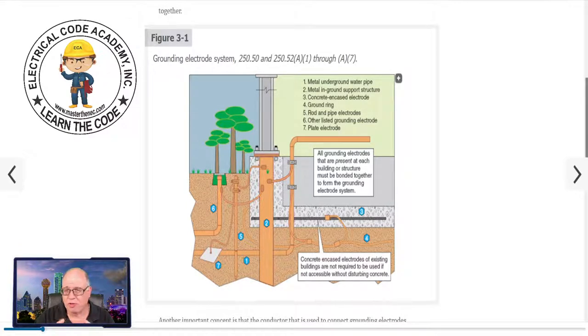Remember, the grounding electrode system we're talking about in 250.50 and subsequently the different ones in 250.52 have absolutely nothing to do with clearing an overcurrent device. This is all about sizing the grounding electrode conductors from the panel down to the electrodes. All of this is based on 250.66. You have some allowances in 250.66 A, B, and C which allow you to have specific sizes given in lieu of using the table in 250.66 — whether you're dealing with rods or pipes, a Ufer ground or ring, you have some allowances. We're going to cover that as we go through this series.